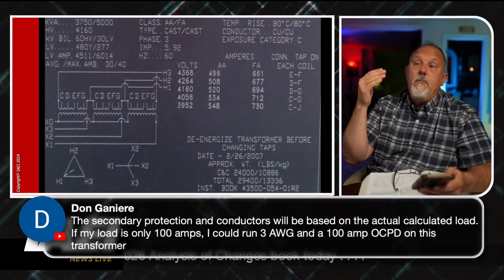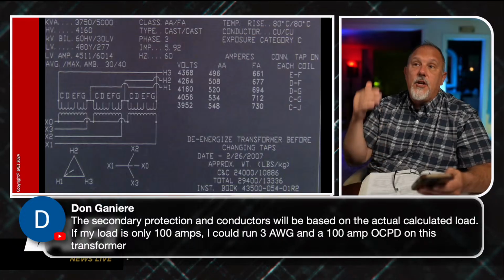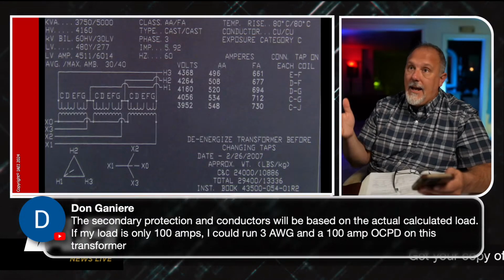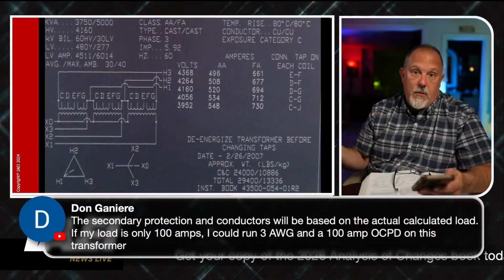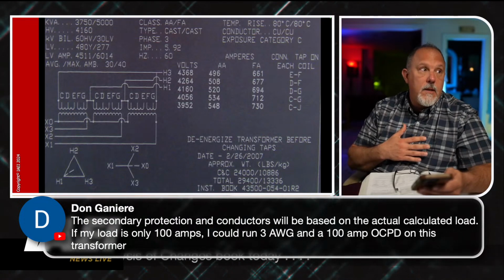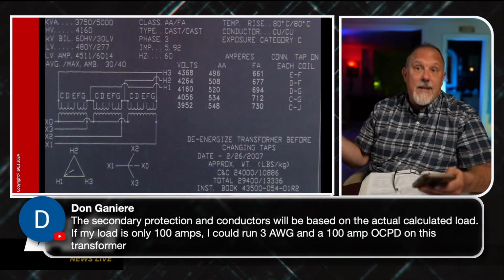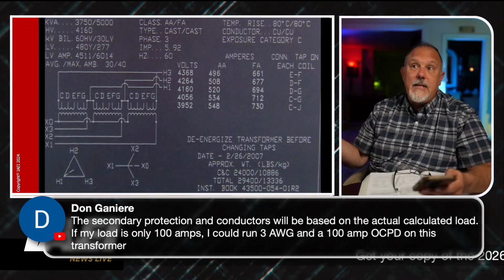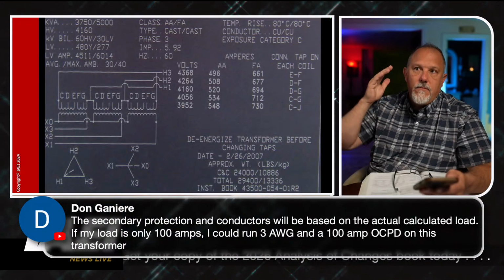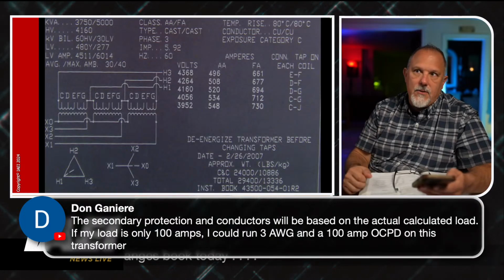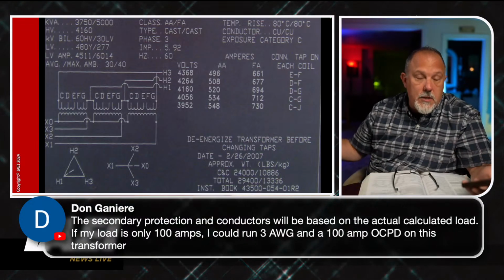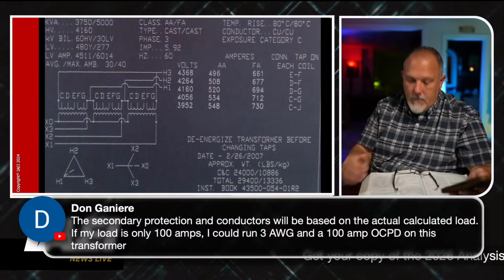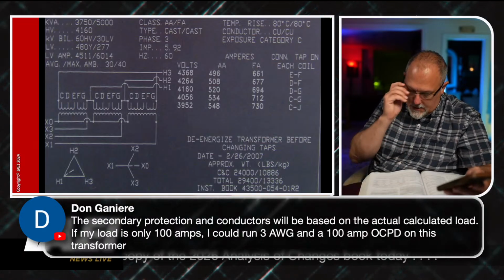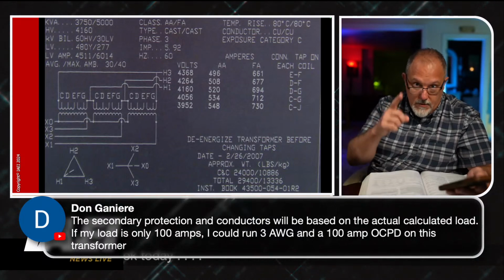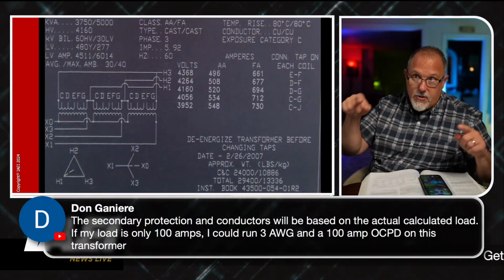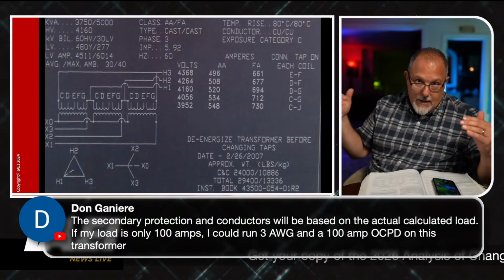So I'm thinking that if you spent money to buy a transformer that can go to 5,000 kVA, if you didn't need more than 3750, you wouldn't have spent the money for it. That's just my gut. And if you spent the money for 5,000 kVA, then your conductors on the secondary have to be able to accommodate the additional load. Whether it's all in one piece of switch gear that can handle whatever amps, or two pieces of switch gear, I don't know. You're allowed 6 disconnects on the secondary, right? And the disconnects can't add more. So your overcurrent protective devices can't be larger than the summation of your full load amps on the secondary.